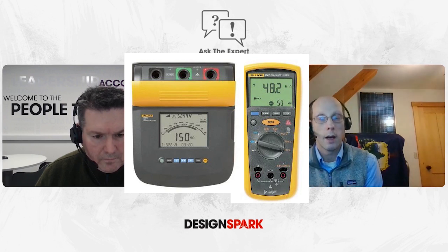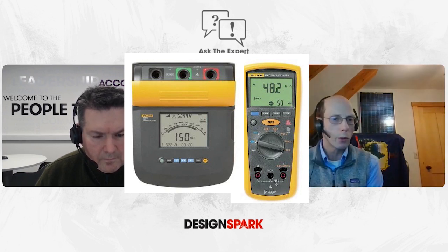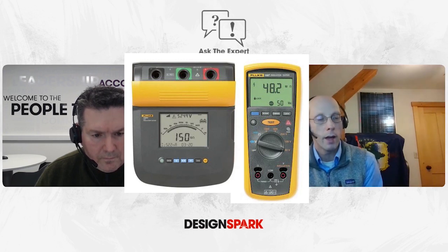Like I said, modules that are running hotter than other modules are typically an indication that there's an issue there. Once we've identified a location that has an issue, we can go in and use a variety of tools to diagnose different problems. We use insulation resistance testers to find intermittent ground faults, which is a wire that has typically had the insulation rubbed bare or been pinched between pieces of metal, and now it's making contact with the module frame or the racking of the array.